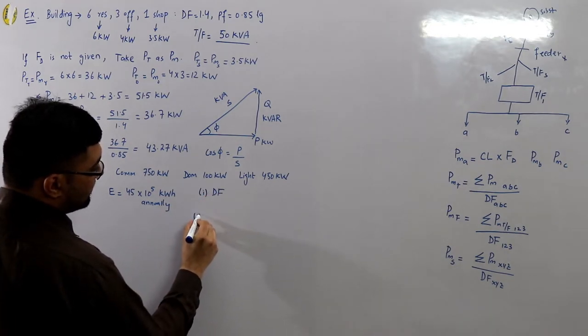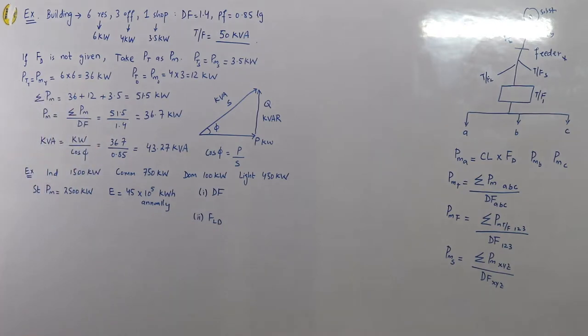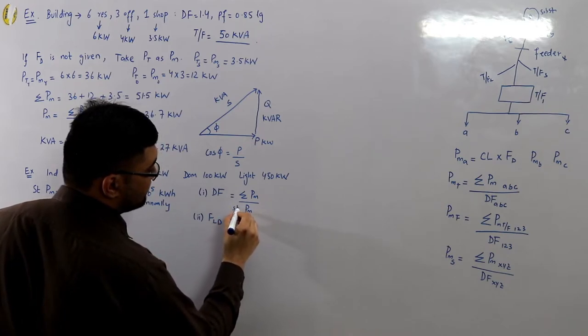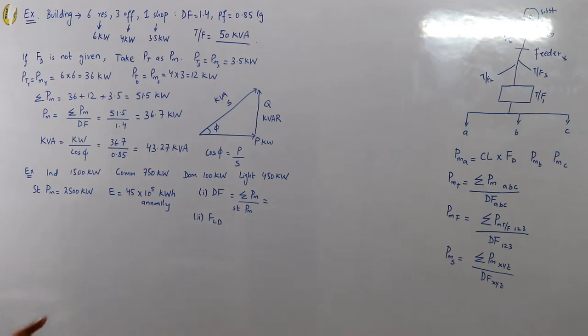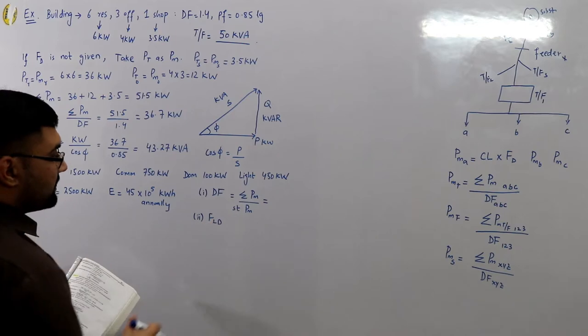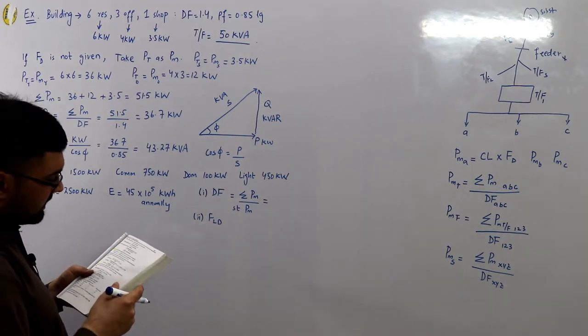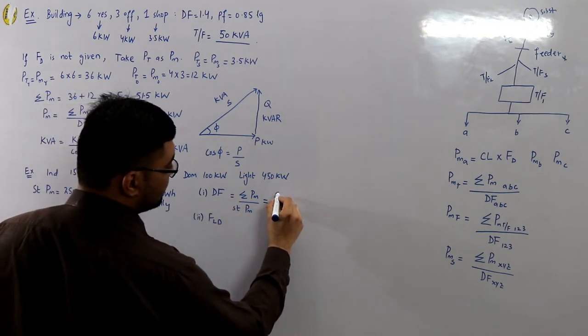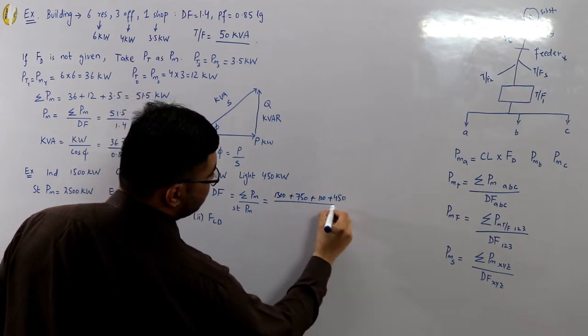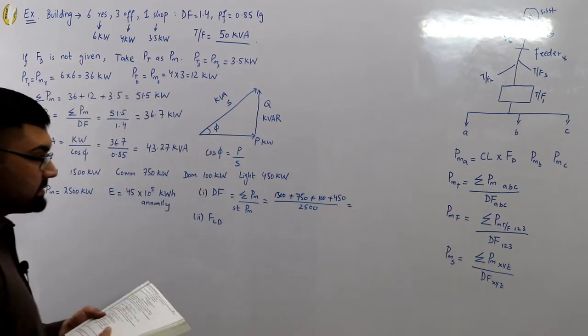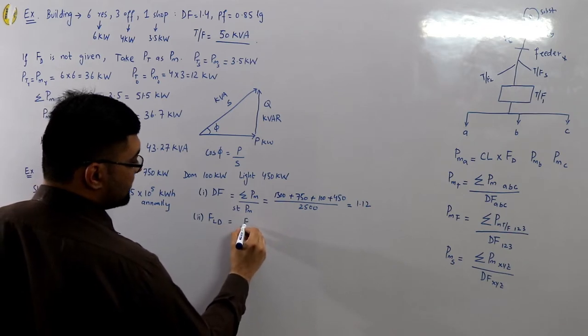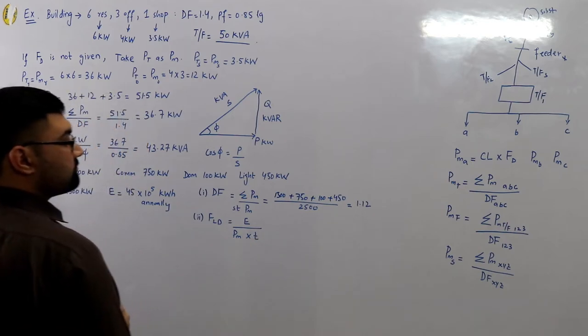The diversity factor = summation of individual maximum demands ÷ maximum demand of the station. Since demand factor is not given, take each load as its maximum demand. Summation = 1500 + 750 + 100 + 450 = 2800, divided by 2500. The diversity factor comes out to be 1.12.